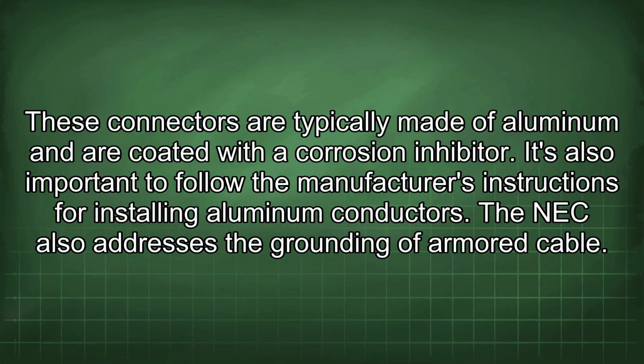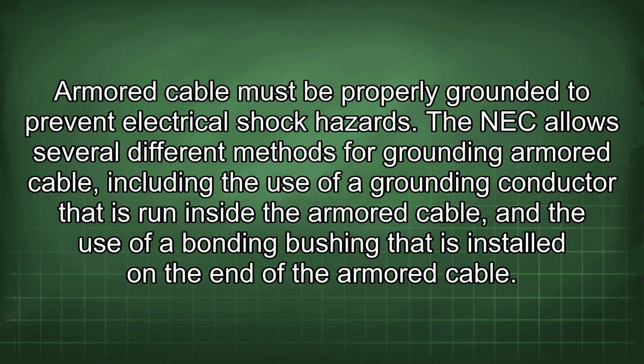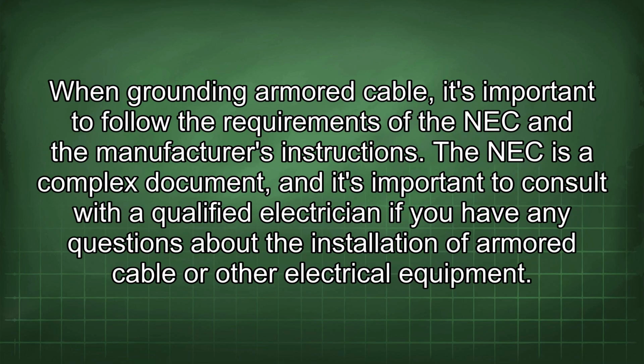The NEC also addresses the grounding of armored cable. Armored cable must be properly grounded to prevent electrical shock hazards. The NEC allows several different methods for grounding armored cable, including the use of a grounding conductor that is run inside the armored cable, and the use of a bonding bushing that is installed on the end of the armored cable. When grounding armored cable, it's important to follow the requirements of the NEC and the manufacturer's instructions.